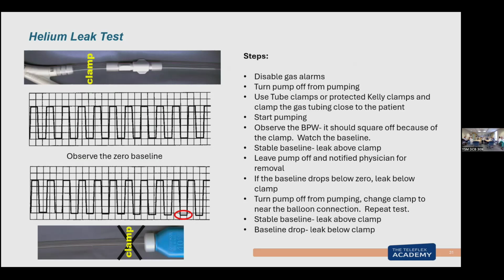If I'm clamped here, and this stays absolutely on 0, I just found my hole in the balloon. I'm only doing this test because I'm getting a possible helium loss 2 alarm every 2 to 3 minutes. So I've isolated the balloon, and I no longer have a drop in my baseline. The problem is my balloon catheter. Well, you guys have got to take the catheter out. I found the hole. There's just no blood in the tube.